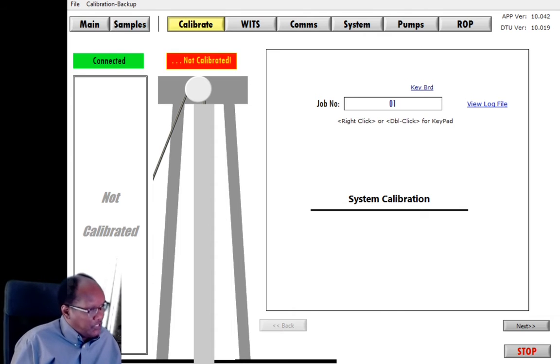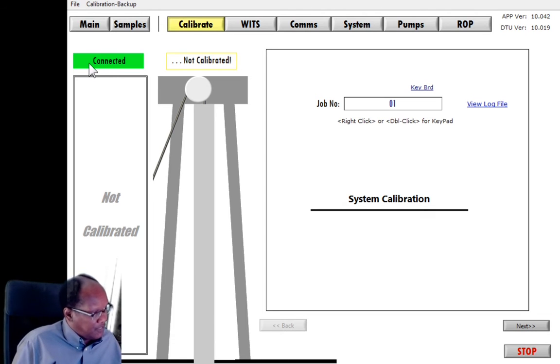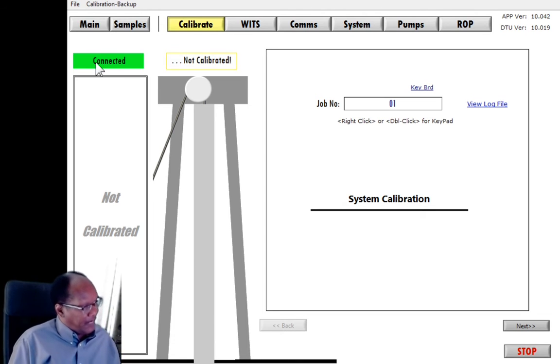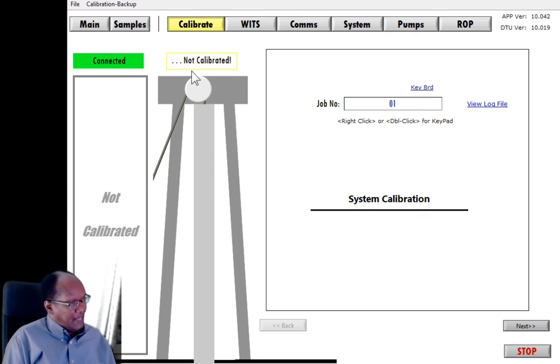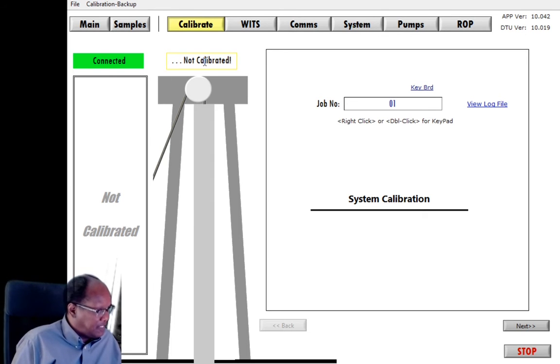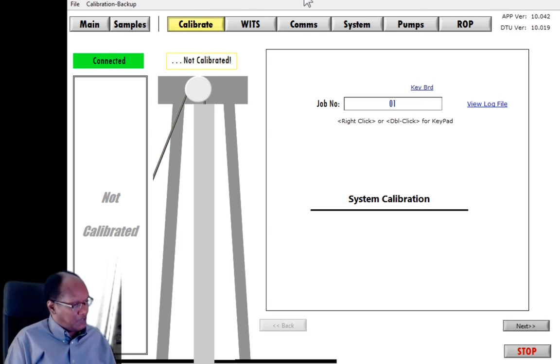The situation shown here is where power has been restored and the software is able to connect to the data acquisition system. You can see the connected indicator turn green, and then you'll get a flashing indicator that the calibration has been lost, in which case you can now do this procedure.